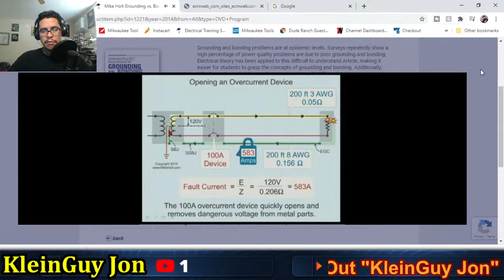This is called an equipment grounding conductor, green wire, EMT, whatever. And then this is going to be called a system bonding jumper, a supply side bonding jumper, which we'll talk about later. These are all titles that, you know what, we don't really care what they're called. What really matters is there's a fault that hits the enclosure, and that fault has to have a conductive path. It's called an effective ground fault current path, from the point of the fault back to the source. And the purpose of this effective ground fault current path is to turn it off. And that's it, guys, that's it, that's the purpose. There you go.